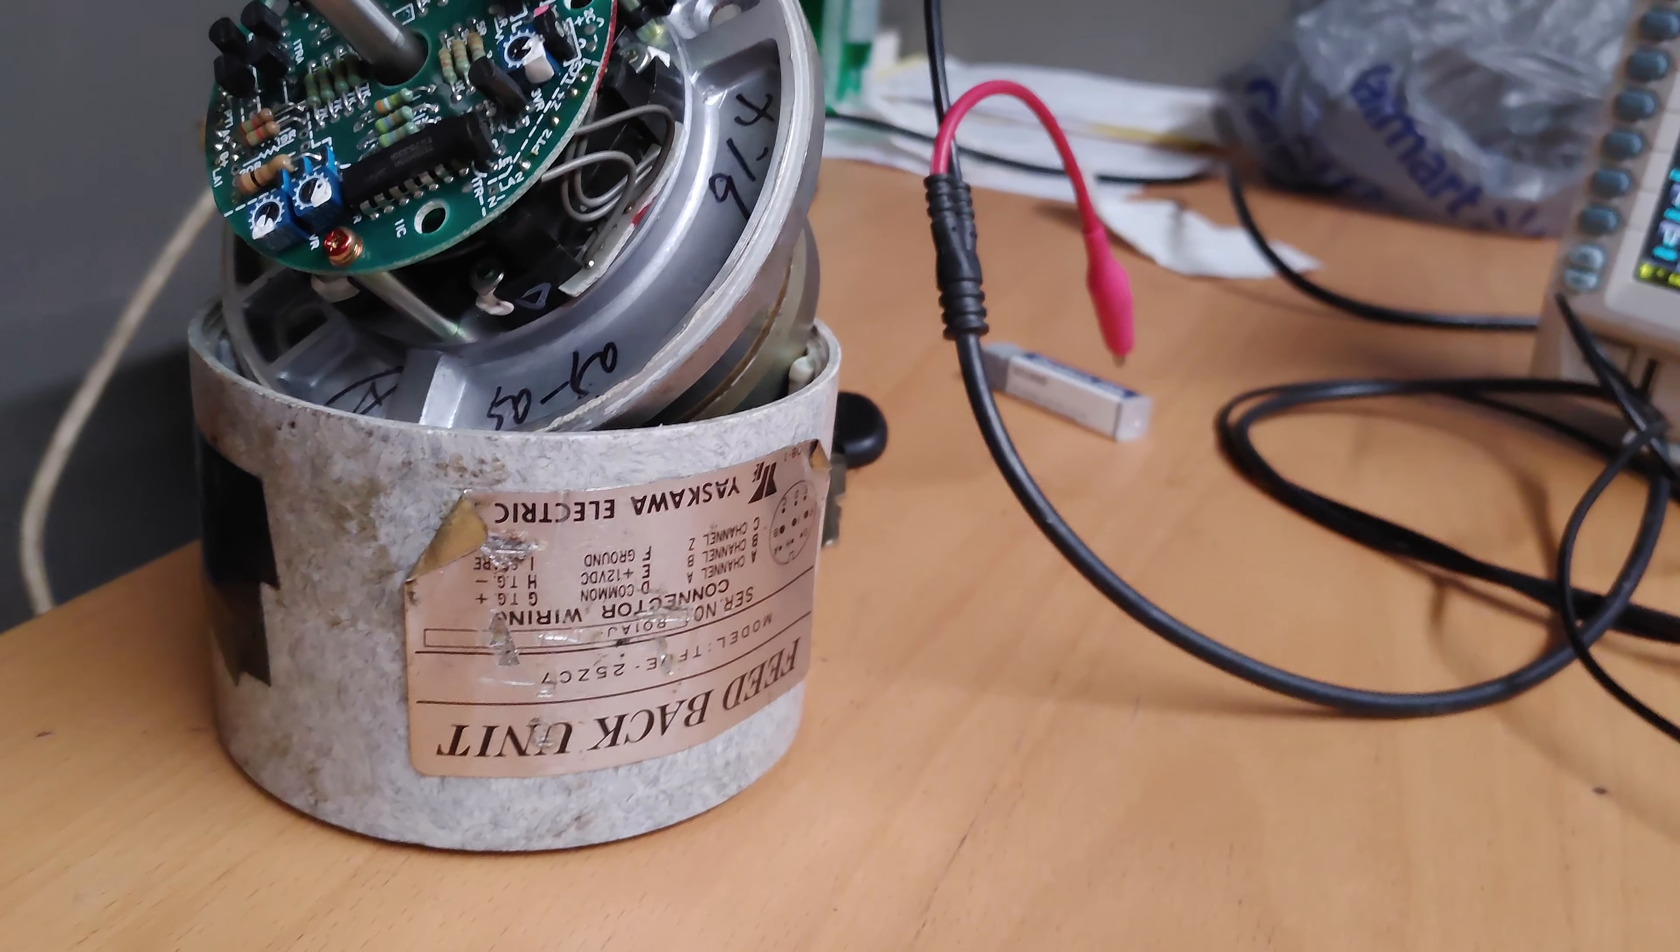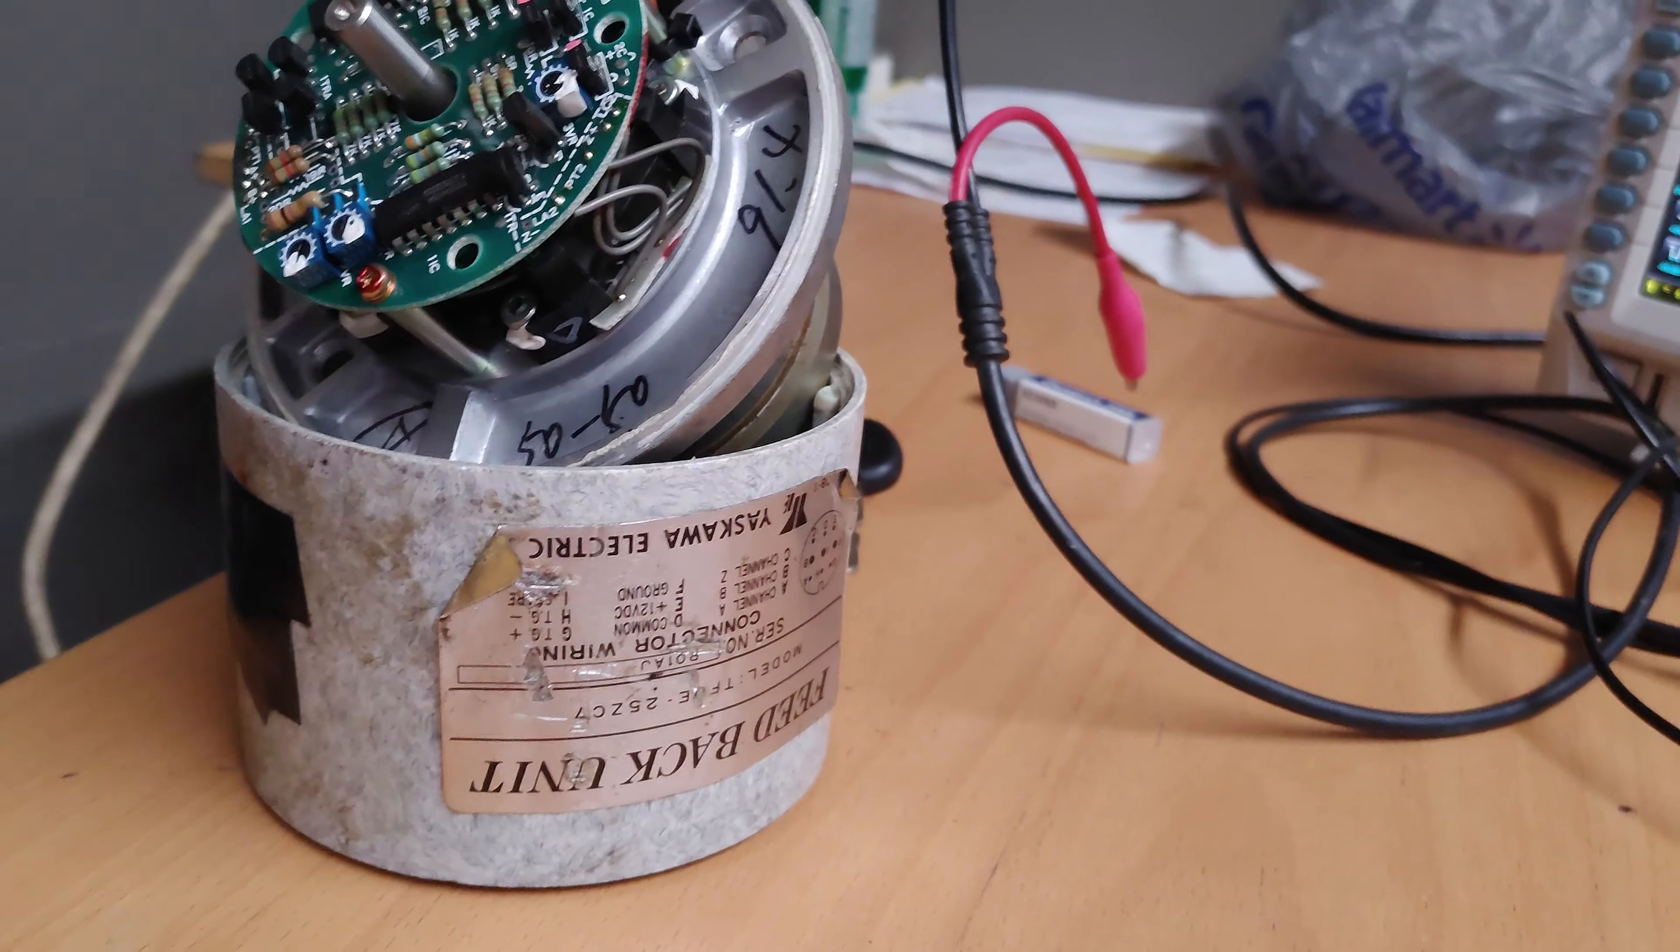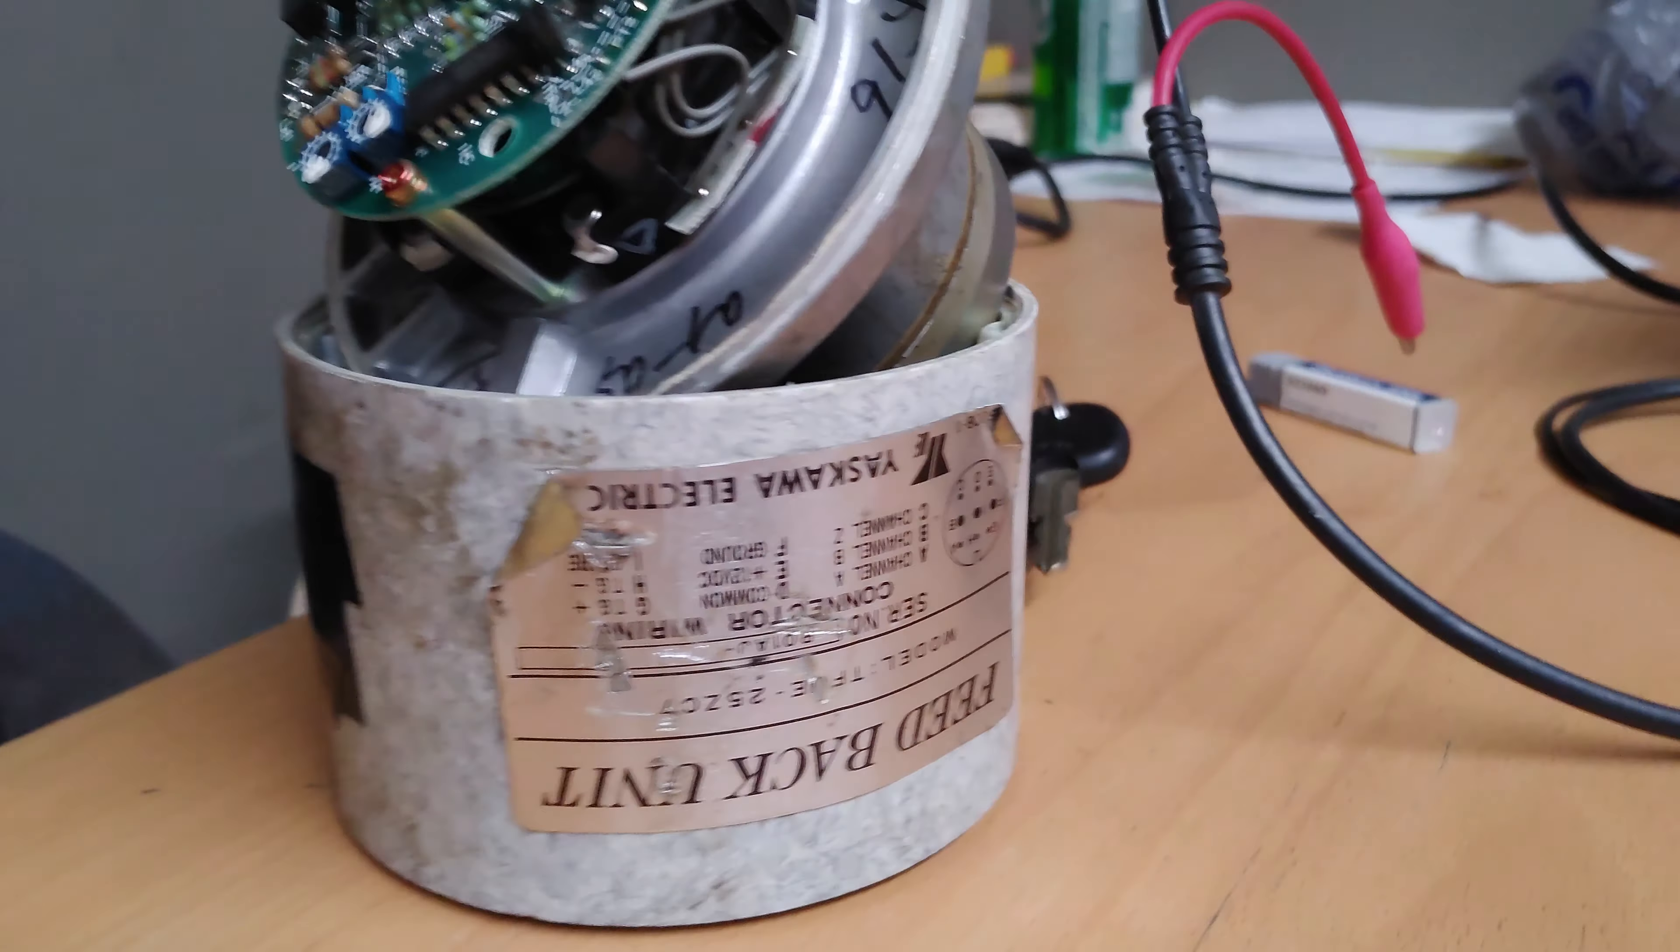I have an old Matsuura mill from 1980 and I keep having issues with it losing its place or not homing properly, or even just strange behavior like the axes are moving. The reason is the encoder.